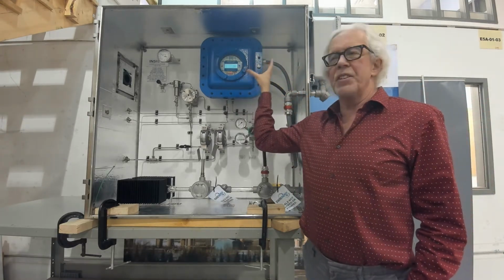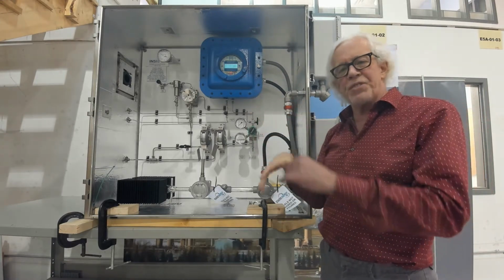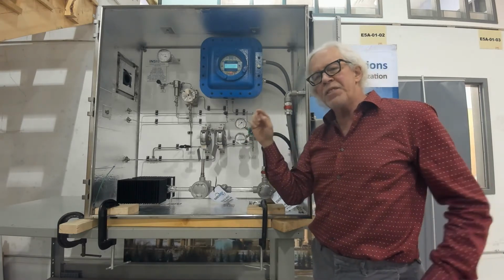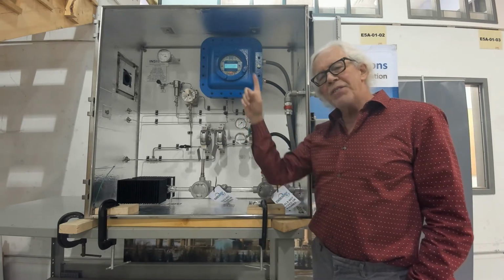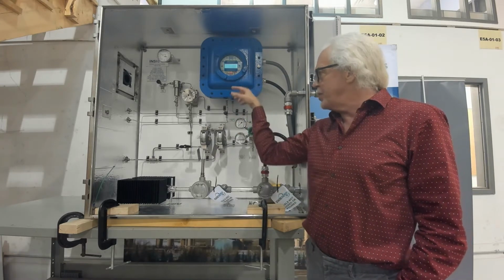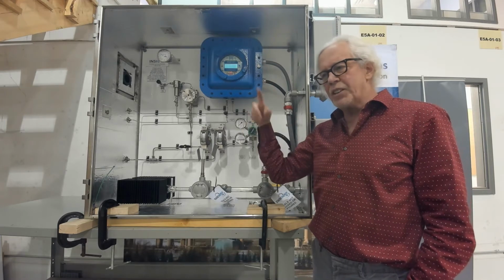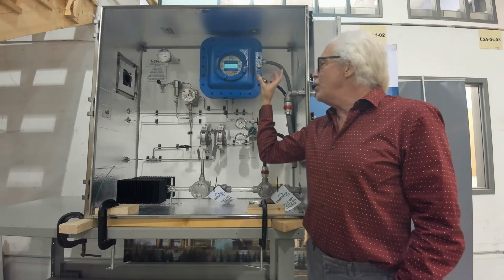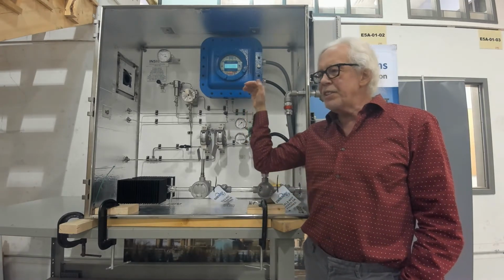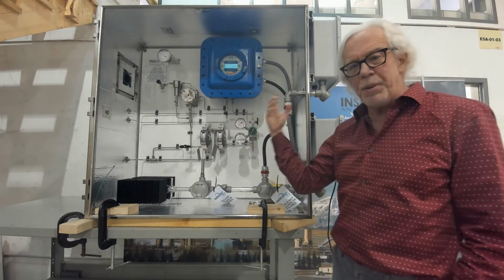At the analyzer, this is our first principles device. It cools an optical surface to let liquids condense on the surface. When the liquids condense, it's bouncing a beam of light off that optical surface, off of a crystal that's inside there, getting what's called internal reflections. And that internal reflection has what's called an evanescent wave. It goes slightly outside of the crystal, and it interrogates the fluid that's being condensed.